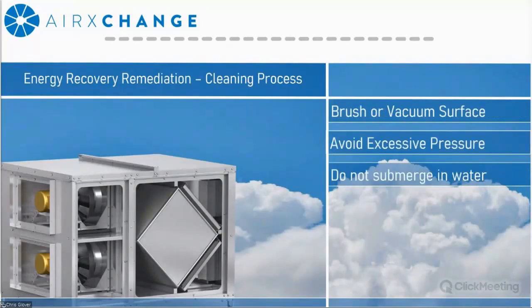The cleaning process for the Airxchange plate is a little bit different. We don't recommend that you wash the media, as that may damage the component. You're going to want to gently brush and vacuum the surface area, taking care not to exert excessive pressure on it. Just like the wheels, we recommend that you do this outside the cabinet, as once again, it's a more hygienic approach so that you don't introduce any potential contaminant into the unit.